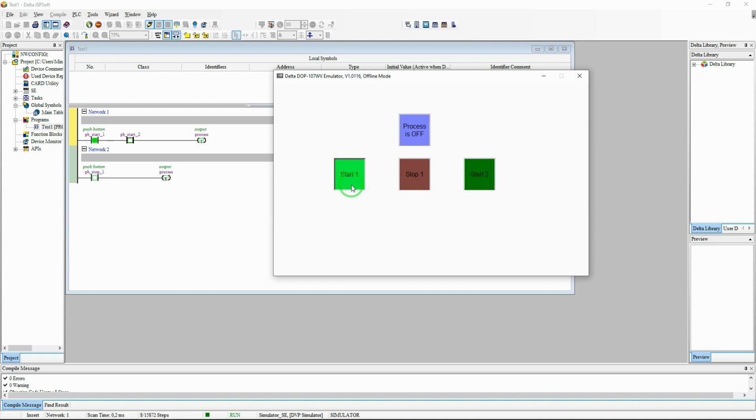Technically you should use safety relays, but if your machine is not very dangerous and it is only safety category 1, you can use this type of example. But what if one button gets stuck in the on position? So I could run it like this, right? Just by pressing one, because this one is stuck in the on position, right?